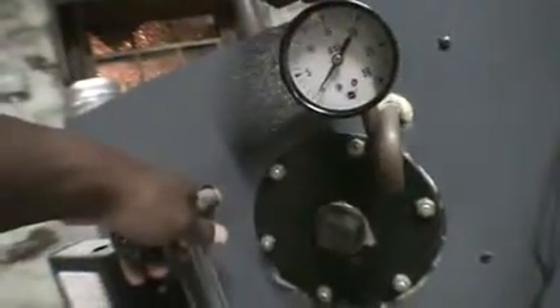Now, with a hot water boiler, you've got the entire boiler filled with water. So that means more of the heat that's coming from the ground or coming from the burner jets is going directly into the water, or more of it is being kept in the water before it actually exits out. That is the only reason why, when it comes down to a cast iron boiler, a hot water boiler will be just a bit more efficient. Not because it's a better make, not because it's a better build. So don't ever let them tell you that bullshit.